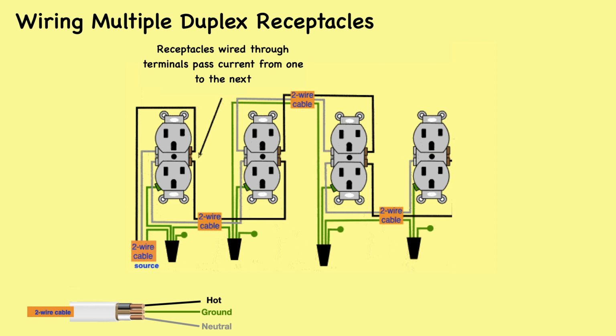The importance of wiring outlets together using the device terminals versus using, say, a pigtail splice: while both methods are commonly used, there is a notable difference in reliability. When outlets are wired together using the device terminals, it creates a daisy chain effect where the current flows through each outlet in a sequence. However, this method can be potentially weak and it has a weak link problem.